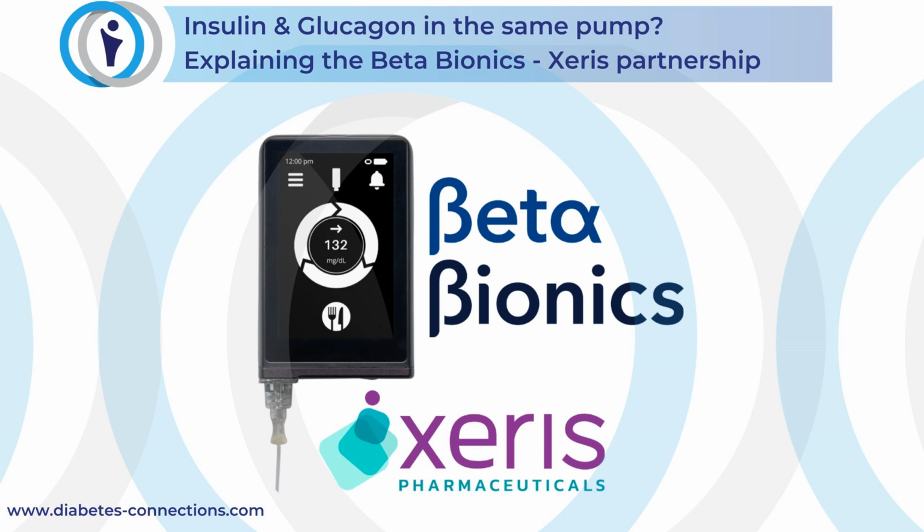Another question I had about the iLet is, since the last time we talked, any changes in CGM compatibility? Since last time we talked, absolutely. We launched with G6. We are now G7 compatible, and we will continue to look at other compatibilities as they become available and make sense. But we ultimately believe in patient choice, of course.